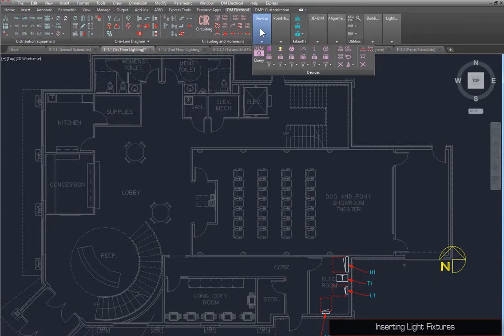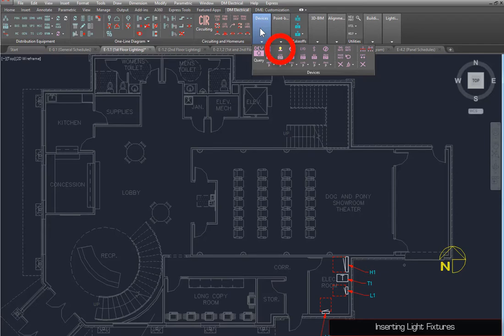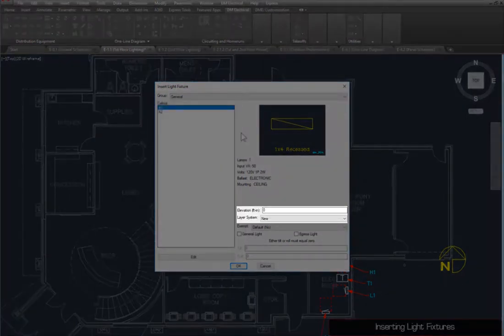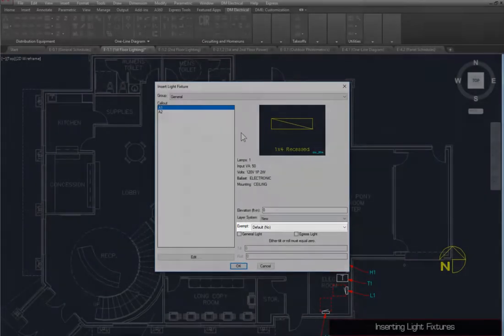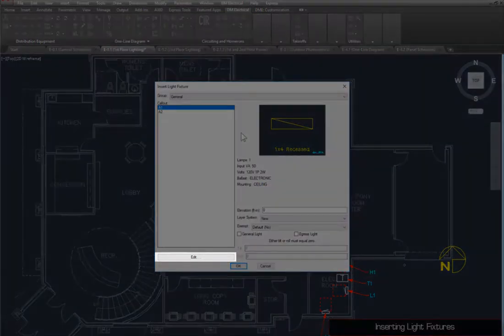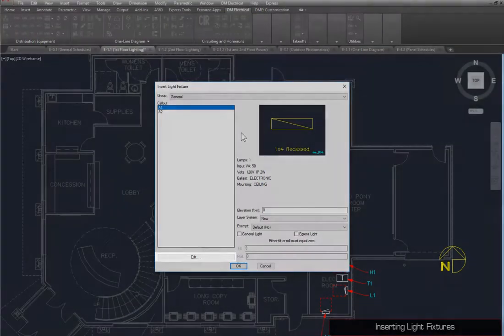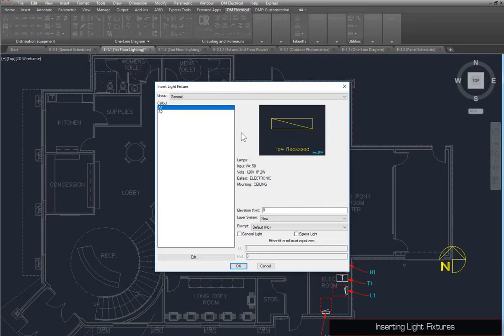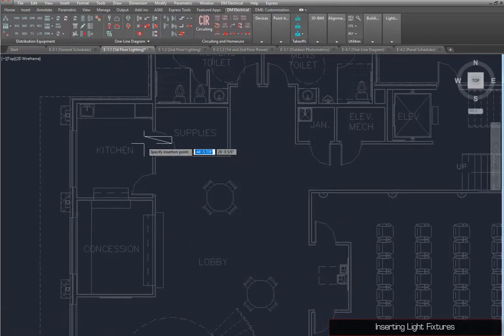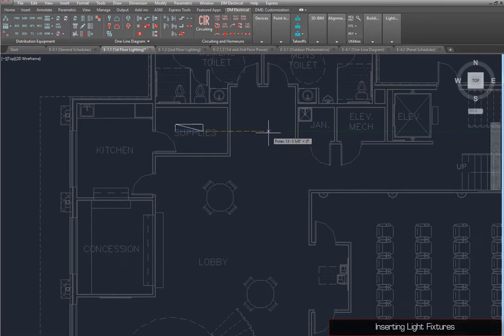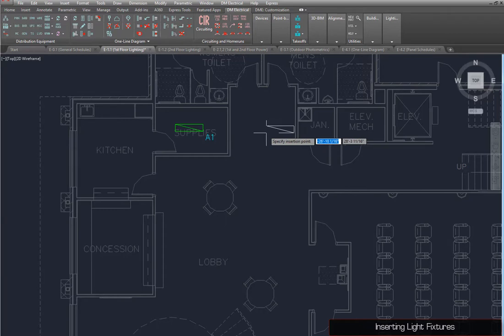To insert light fixtures and most other devices, use the Insert command for the device type. Here, you can select the light fixture to insert, set the Elevation and Layer system, whether the fixture is included in energy calculations, and additional information used for point-by-point photometrics, which will be covered in Part 7. You can also press the Edit button to make changes to the selected fixture in the schedule. Select light fixture A1 and press the OK button. Specify an insertion point and rotation angle for the fixture. Place as many fixtures as you need, then press Enter to finish the command.